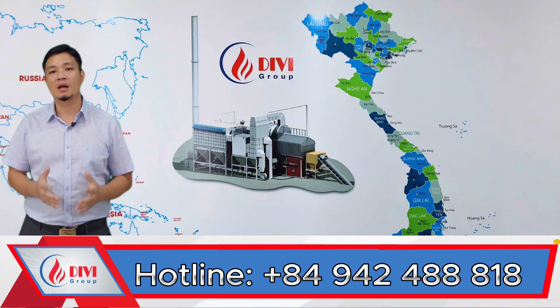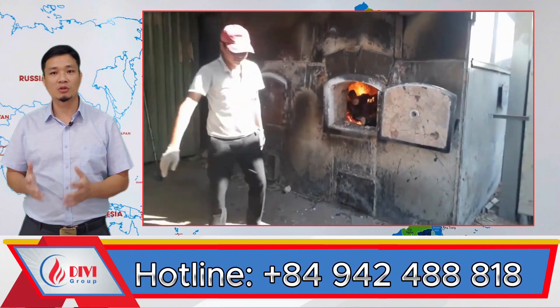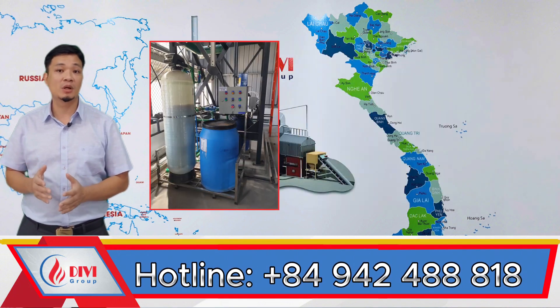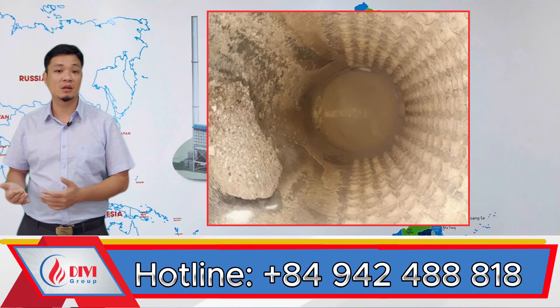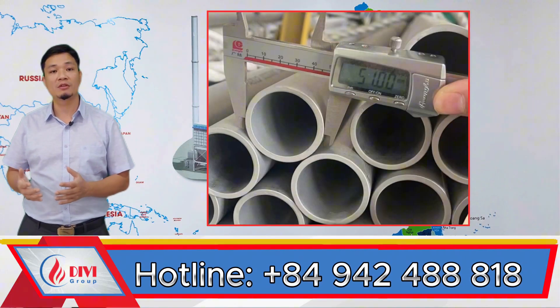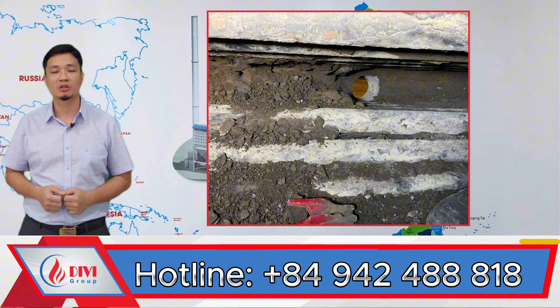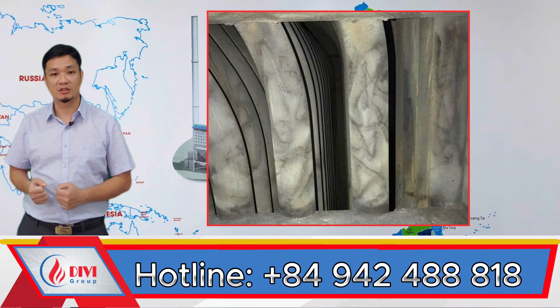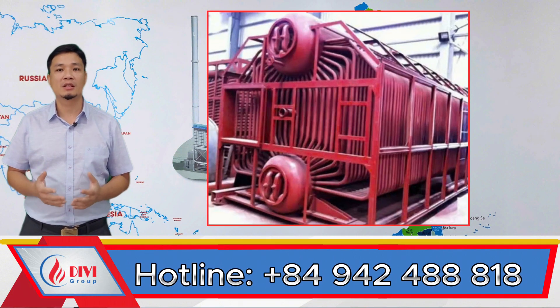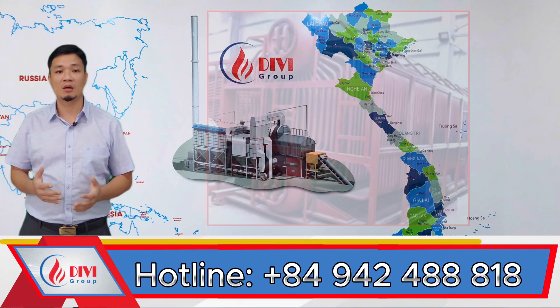But back then, the level of understanding in Vietnam regarding boiler water treatment and operation was still quite limited. Most factories simply installed the boilers, loaded fuel, turned on the fan, and that was it. Things like proper water treatment, blowdown, and internal cleaning were often overlooked. As a result, these water tube boilers degraded very quickly, particularly because their steam-generating tubes were mostly 51 mm in diameter, which is relatively small. Scale formed rapidly on the inner surfaces, causing tube blockages or even tube ruptures, which severely disrupted production. One of the biggest weaknesses of the traditional two-drum water tube design is that it's very difficult to replace individual tubes in the convective section. When a tube gets damaged, it typically has to be plugged instead of replaced. So over time, as more and more tubes are taken out of service, the boiler's steam output gradually decreases.